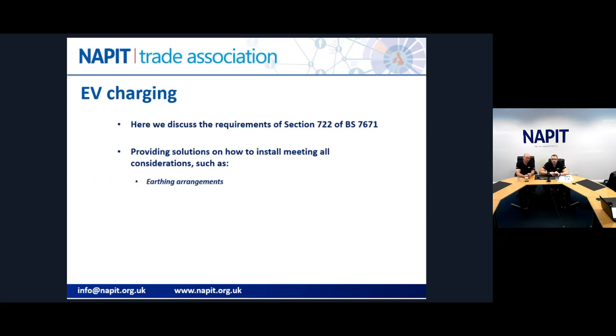We talk about earthing arrangements - there's a lot of discussion about what type of earthing you can and can't use, and the different types of RCDs, because with some of this equipment the batteries' DC can leak back through, so we need the correct type of RCD. We discuss different earthing arrangements, like putting an earth rod in outside, and whether you can get simultaneous contact shock risks - so the favourite, the outside light and tap, be careful with these things. It's all discussed in the book.